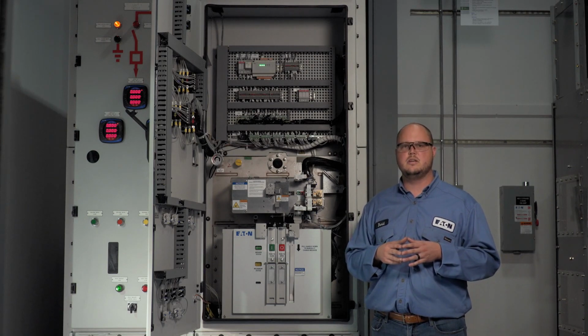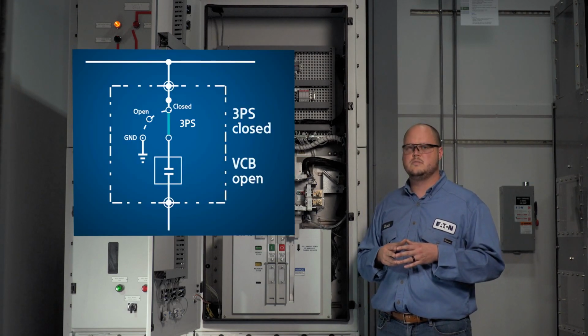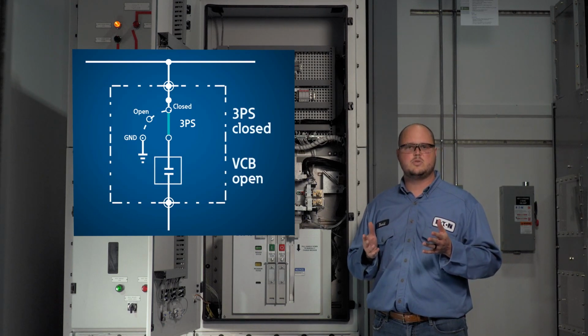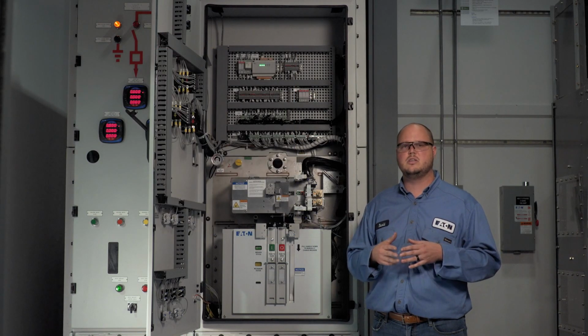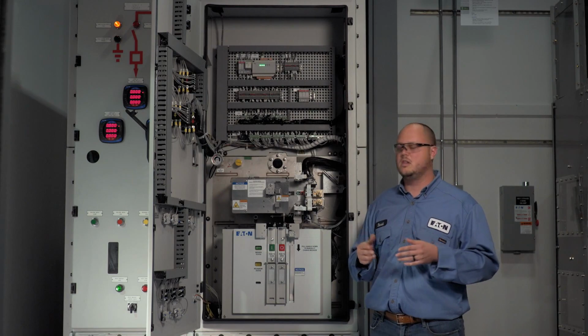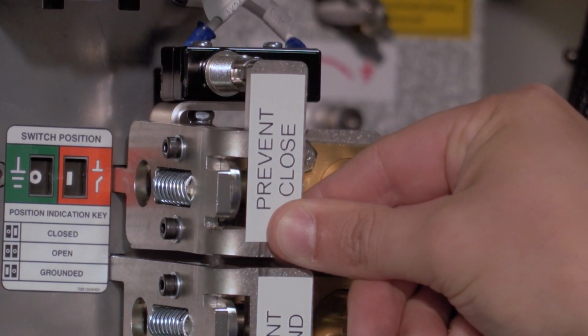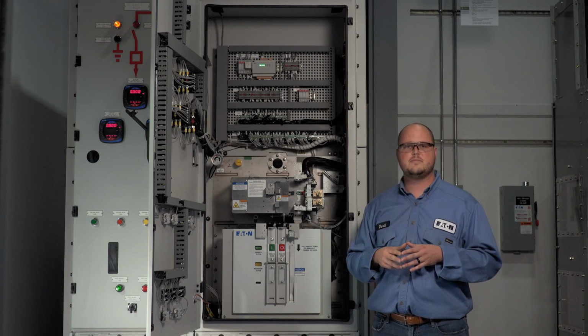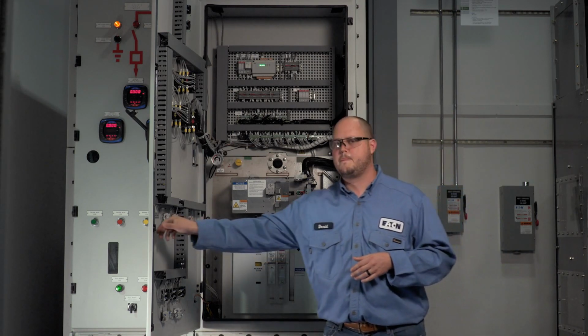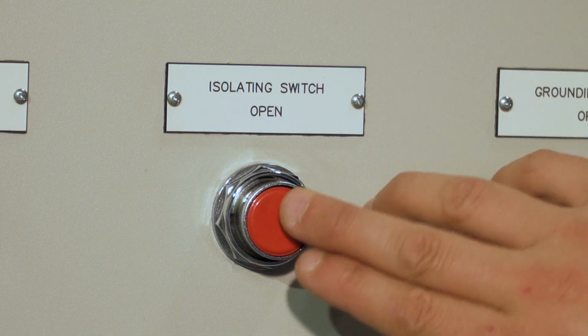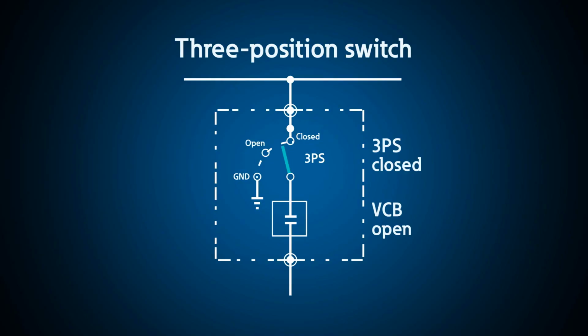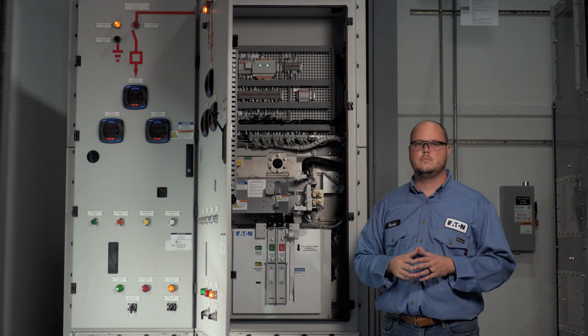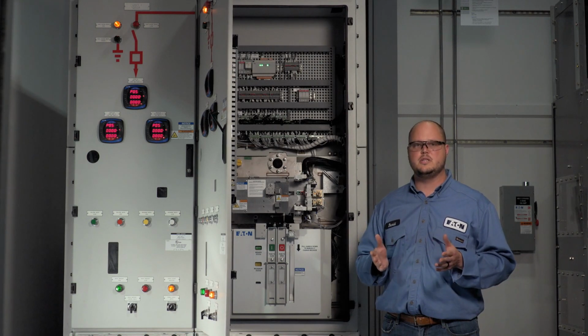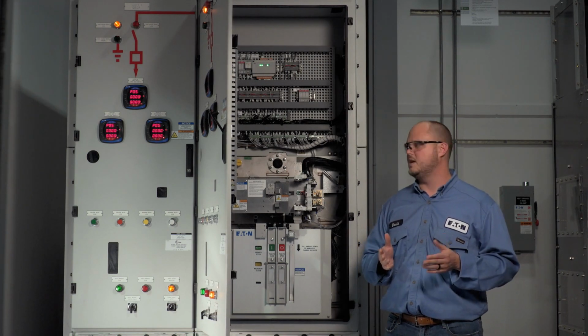The circuit breaker is currently open and the 3-position switch is closed. One very important feature of these 4 switch locks is that they cannot be applied unless the switch is in the proper position. Because the switch is currently closed, I cannot apply the prevent close lock. I must first open the 3-position switch. After the switch reaches the fully open position, the prevent close lock can then be engaged.